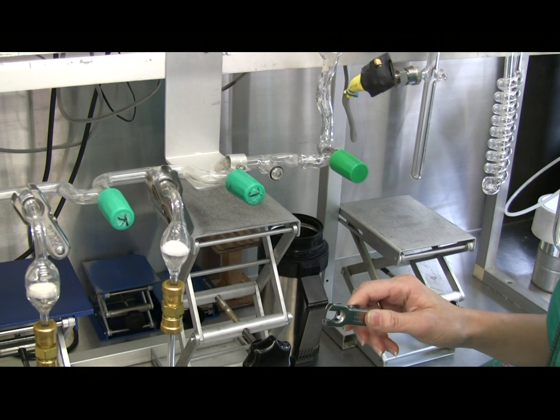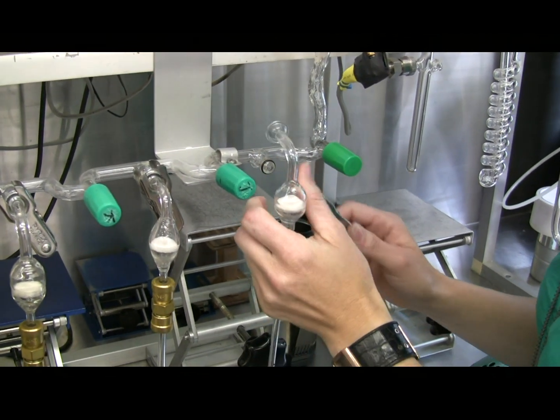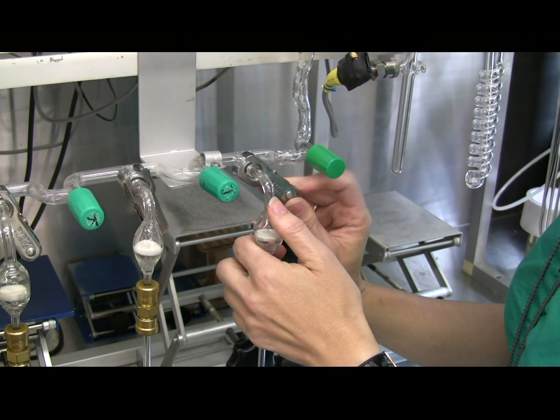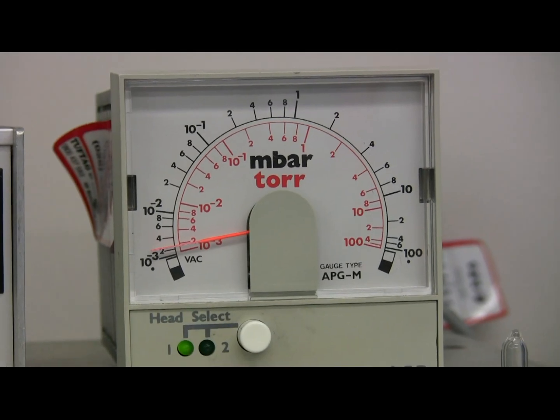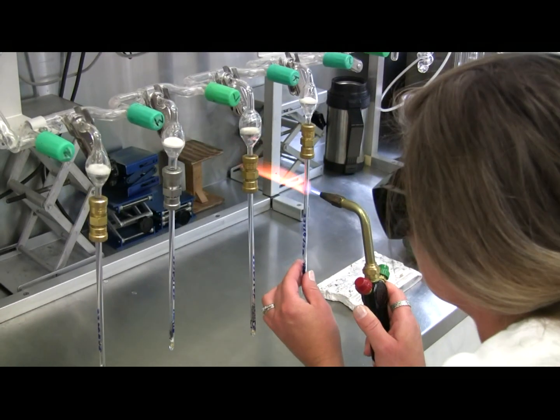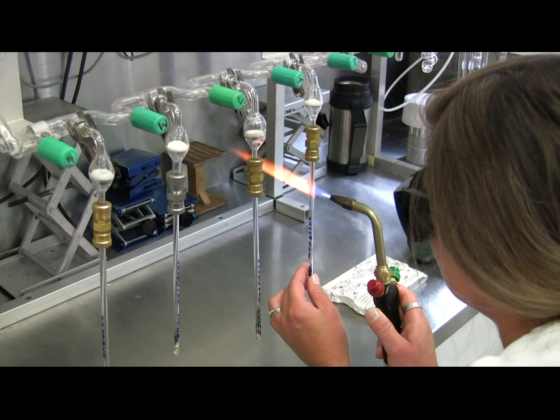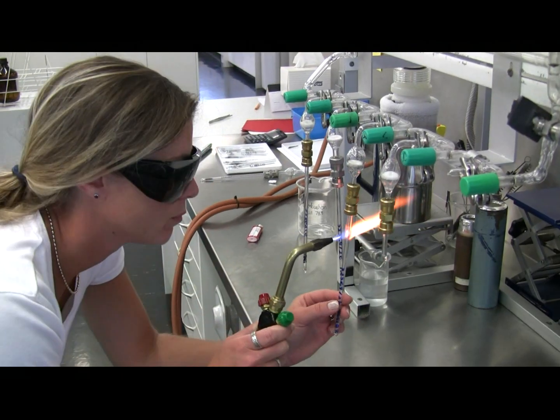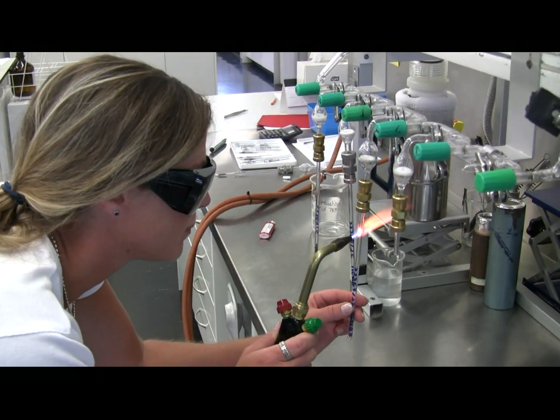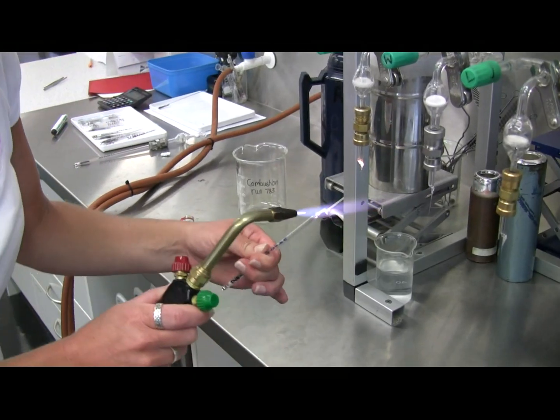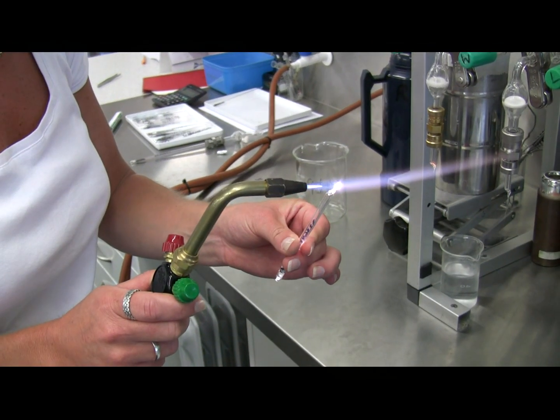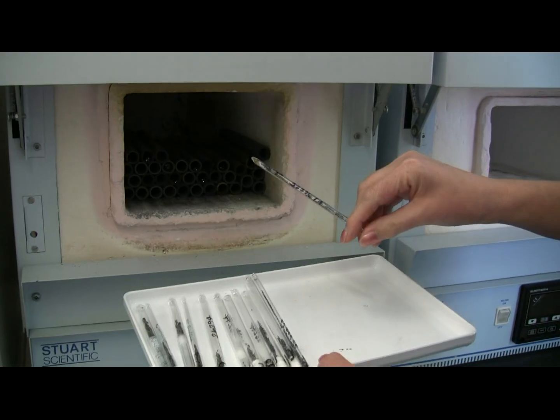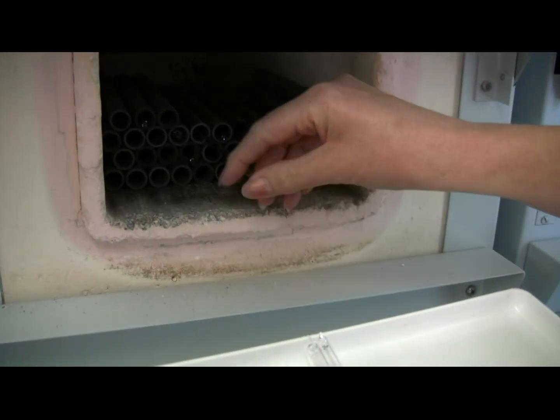Then we put that combustion tube on a vacuum line and we pump all of the air out of the tube. When all of the air has been sucked out of the tube, we can flame seal it, and that leaves a vacuum on the inside.